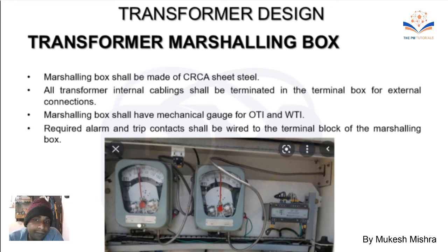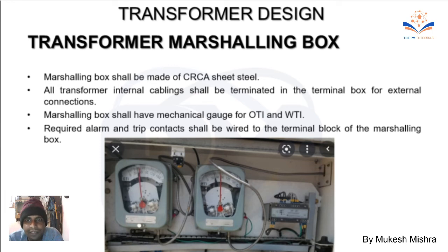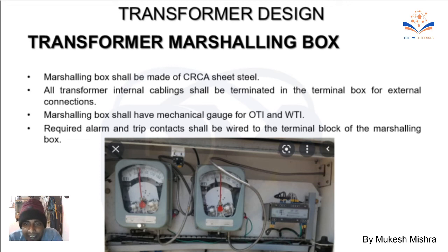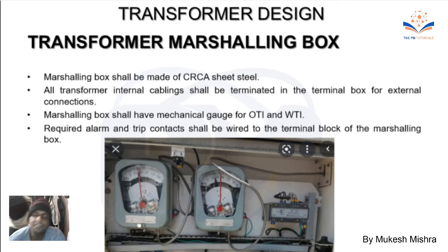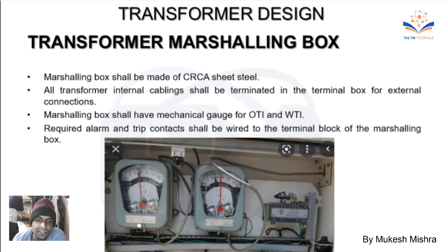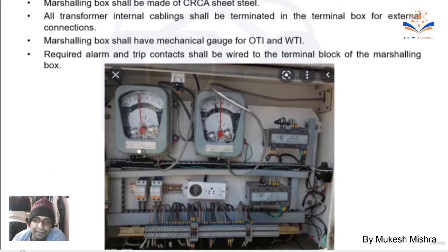The marshaling box should be made of CRCA sheet steel. All internal cabling should be terminated in the terminal box for external connection. The marshaling box shall have mechanical gauges for OTI and WTI. Required alarm and trip contacts shall be wired to the terminal block of the marshaling box.